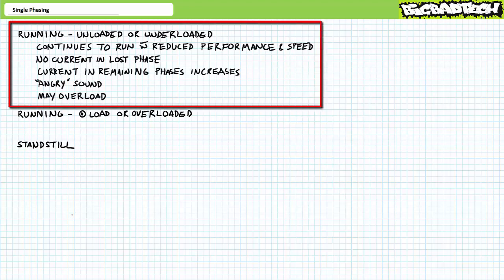Ordinarily, an unloaded motor single phased while rotating will continue to run, but at a reduced speed and will draw excessive current in the remaining phases — no current will be drawn in the lost phase. Additionally, the motor will produce an ugly growling or crackling sound. Given current in the remaining phases increases, overload elements may eventually signal an overload, although it may take some time. Lacking overload protection, this motor might eventually damage itself over time.